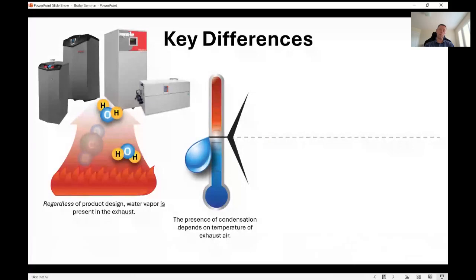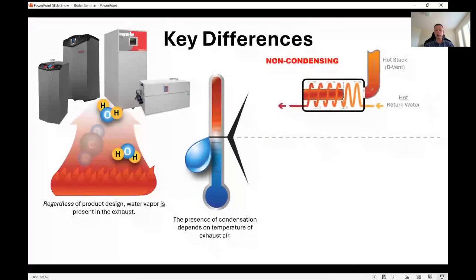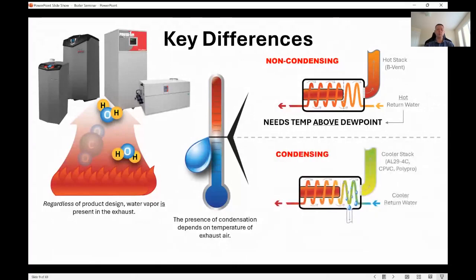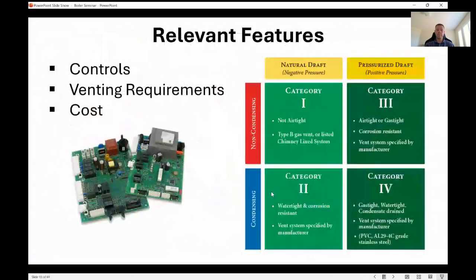The other one can operate below the dew point, but it's just not going to last you very long, right? The other thing you have to consider is your stack, almost more important than the boiler. If you're going to be operating in condensing mode with a condensing boiler, you are going to need a stack that can handle condensate. That's generally going to be stainless steel, CPVC, or polypropylene. A lot of non-condensing boilers won't have those types of stacks. They'll use something like a type B vent, which is fine in non-condensing mode. But if you actually do condense in there, it's going to rot out your stacks.